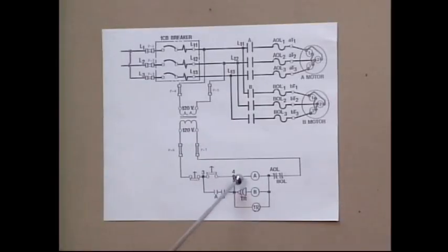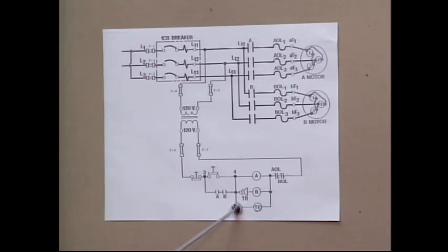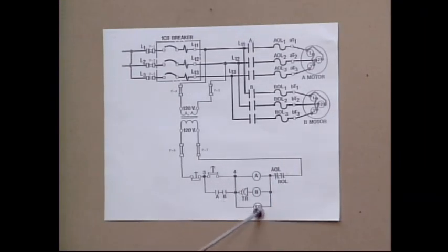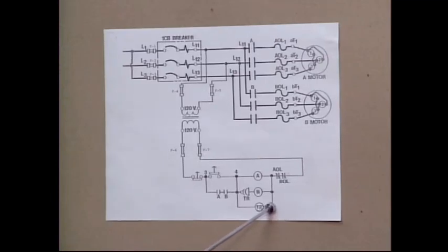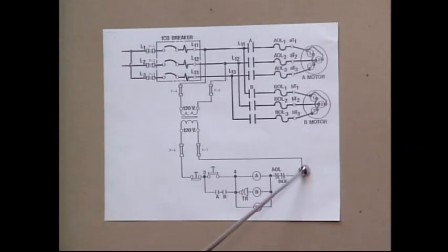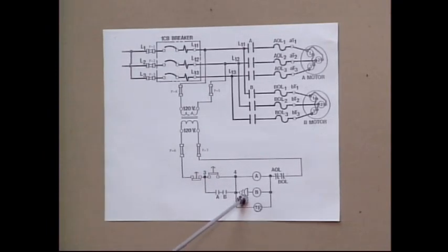Now, before B can go, the timer, which is the coil for the timer, is energized at the same time A is. They're simultaneously operated, A and the timer. The timer is energized. We heard it operate, and it has a circuit. We heard this connection made, but B didn't go.